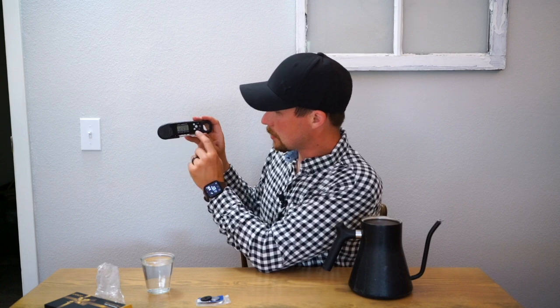That reading is in Fahrenheit. It looks like you can hit this lower button to change it to Celsius, as well as calibrate it. There are instructions in here on how to calibrate it, but typically you fill a glass with ice water and stir it so it's exactly 32 degrees Fahrenheit or 0 degrees Celsius, then go through the calibration process to tell the device that this fluid is at that temperature, which calibrates your thermometer.